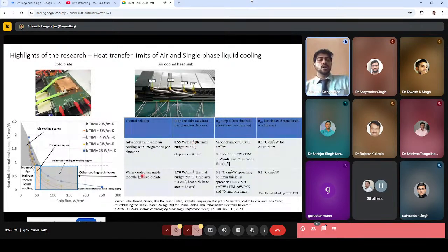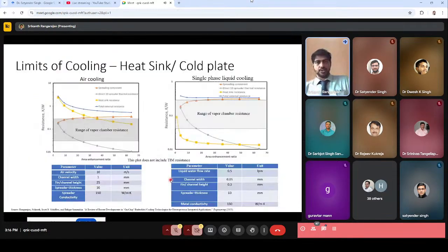For water cooling, a liquid cooled cold plate single phase system, we're able to remove 170 watts per centimeter square for the same thermal budget of 50 degrees Celsius for a 4 centimeter square chip area. These are the results published so far, and we continue working to establish cooling limits for other cooling technologies.